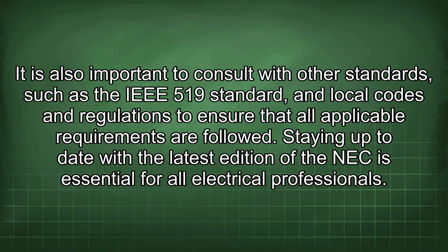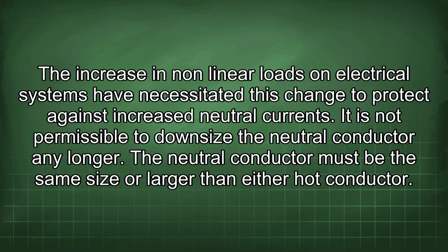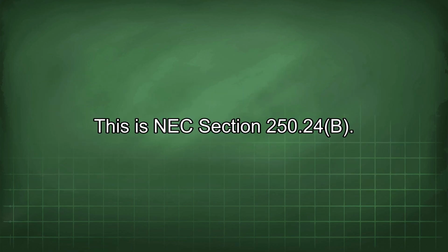Staying up to date with the latest edition of the NEC is essential for all electrical professionals. The increase in nonlinear loads on electrical systems has necessitated this change to protect against increased neutral currents. It is not permissible to downsize the neutral conductor any longer. The neutral conductor must be the same size or larger than either hot conductor. This is NEC section 250.24(B).